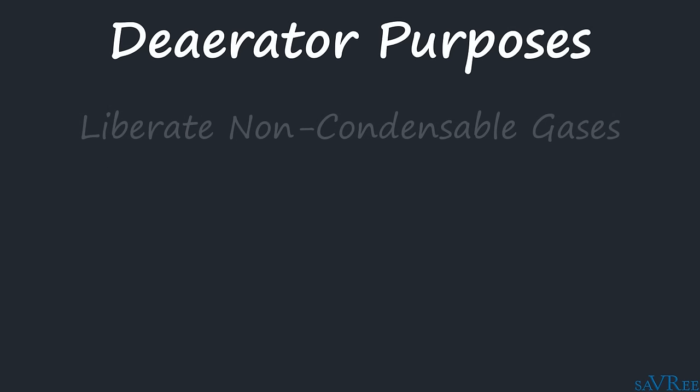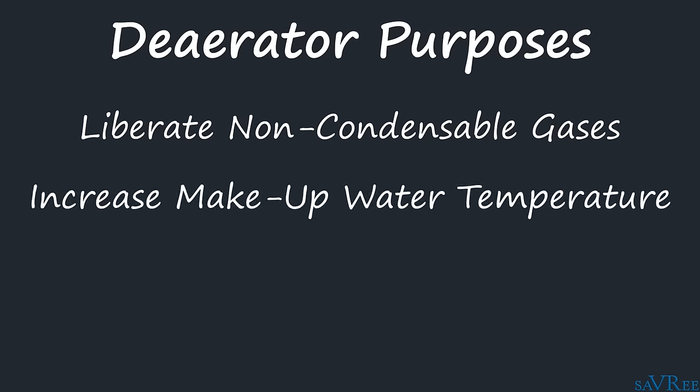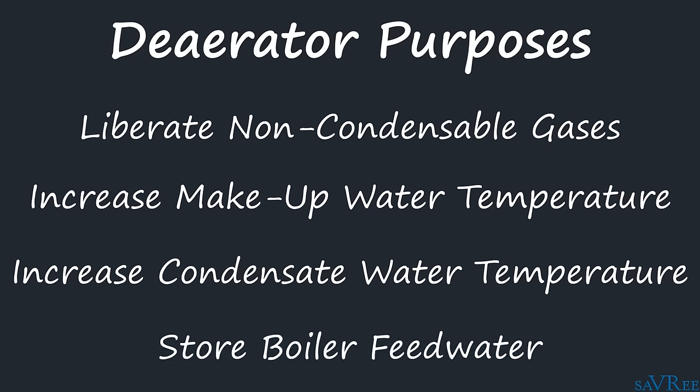A deaerator has three main purposes. Its primary purpose is to release non-condensable gases from the boiler feed water. Its secondary purpose is to heat the incoming makeup water before it's sent to the boiler, and to heat the condensate returned from the steam system before it's sent back to the boiler again. Its third and final purpose is to allow us to store a certain amount of water that can be sent to the boiler as steam demand fluctuates, giving us a storage capacity of boiler feed water.